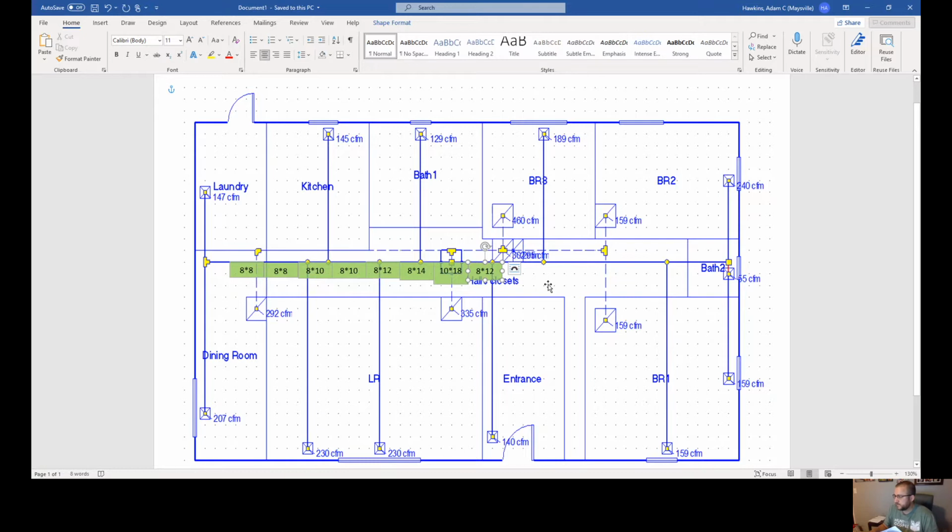Okay, did anything come out of that one? Yes, this one down here by the door did. So the door, we said that was 50. We were going to change that number. So the door took out 50. So now we have how much left? We take off 50 of 500, we should have 450 left. So 450 left is about a 10-inch round, or an 8 by 11. So I'm probably still going to keep that 8 by 12.